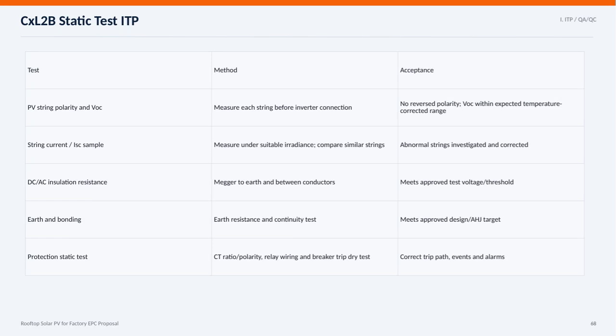Here we have the CXL2B static test ITP for the rooftop solar PV system proposed for the factory. This section focuses on the quality assurance and quality control procedures to ensure system reliability. The key tests include checking the PV string polarity and open circuit voltage, where we must confirm there is no reversed polarity and the voltage falls within the expected temperature-corrected range.